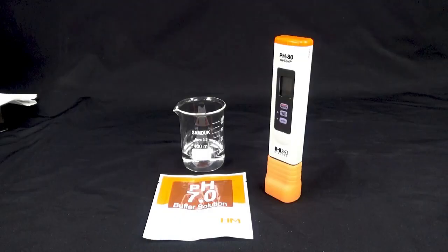Proper calibration of the PH80 is essential for accuracy and optimal performance. The meter comes factory calibrated to pH7 for your initial convenience. When calibrating, choose a level that matches what you will be testing or is within the middle of your expected pH range. Calibrating the PH80 once a month is recommended. The PH80 features an auto-calibration function for pH 4, 7, or 10 buffer solutions. For 2-point calibration, you must calibrate with pH 7 first.